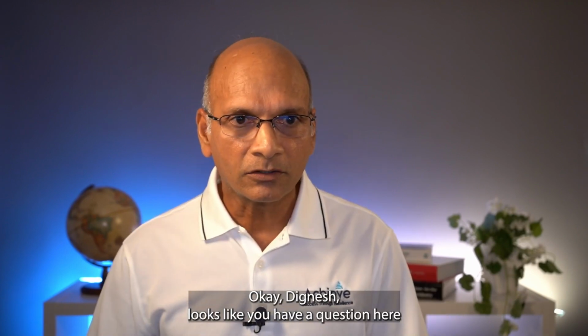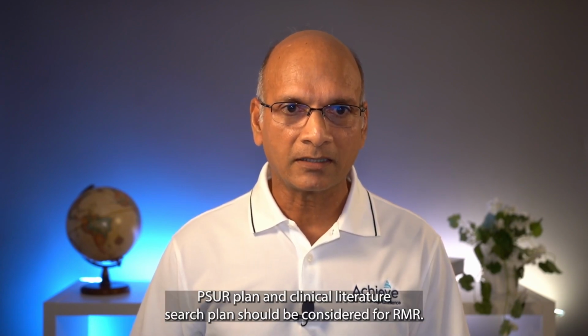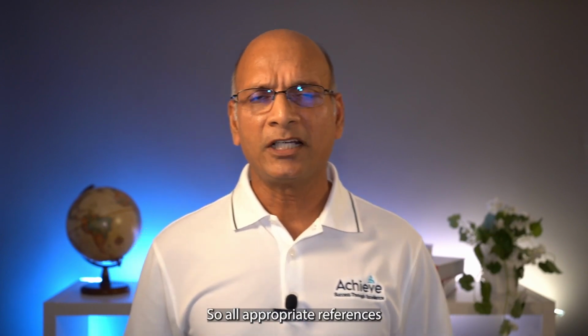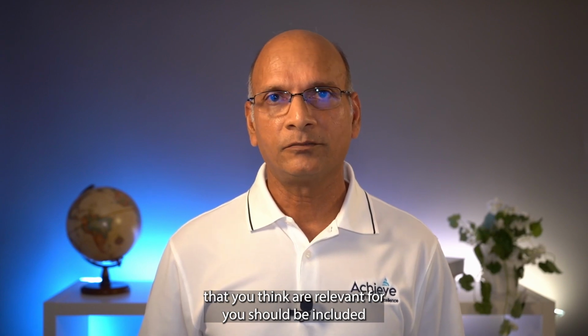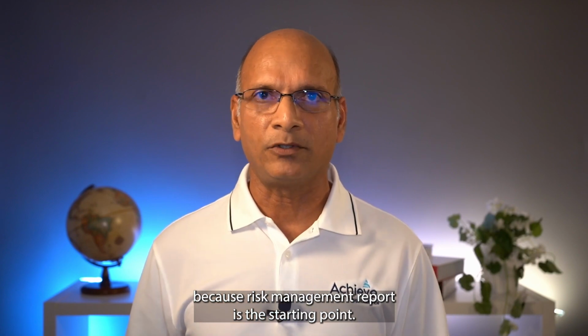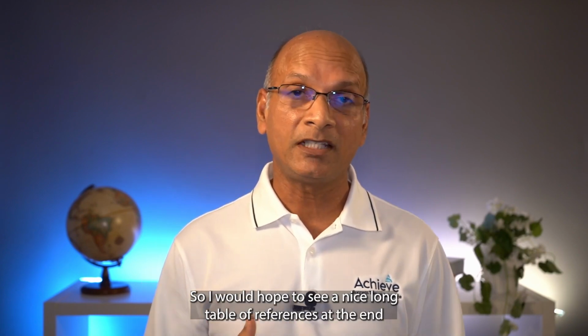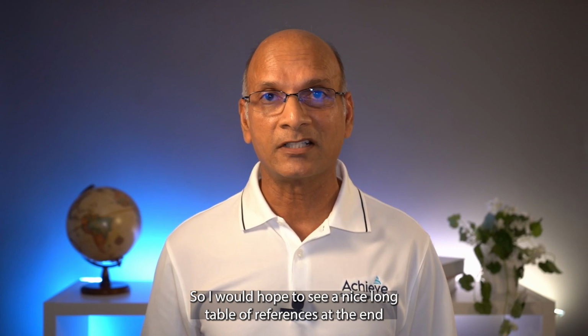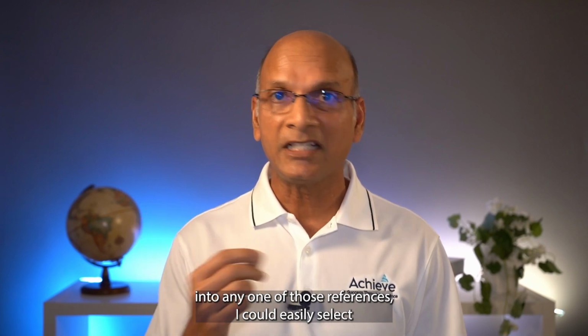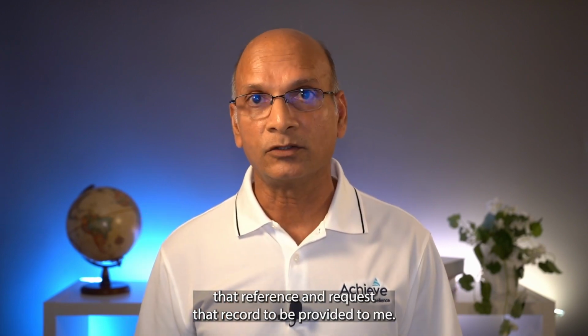Okay, Dignesh, looks like you have a question or a comment. References to PMS plan, PMCF plan, PSUR plan, and clinical literature search plan should be considered for RMR. So all appropriate references that you think are relevant should be included, because the risk management report is the starting point. I would hope to see a nice long table of references at the end, where if I decided to pursue more detailed inquiry into any one of those references, I could easily select that reference and request that record to be provided to me.